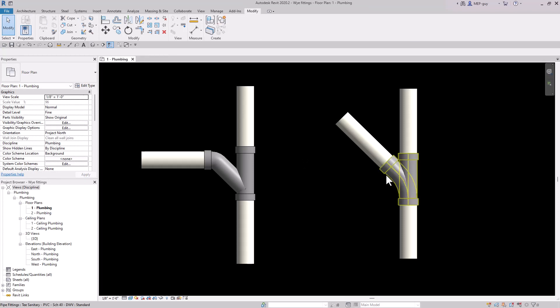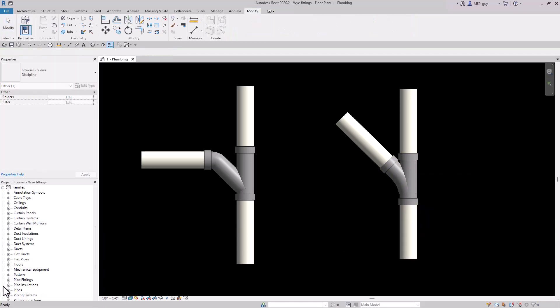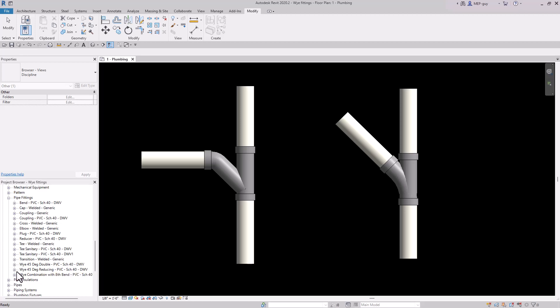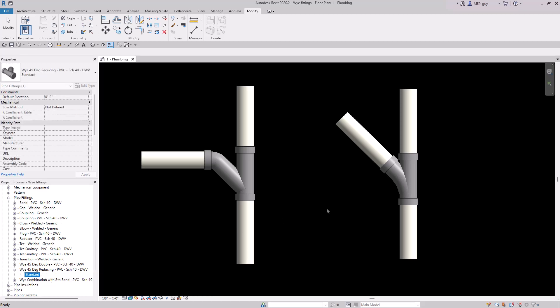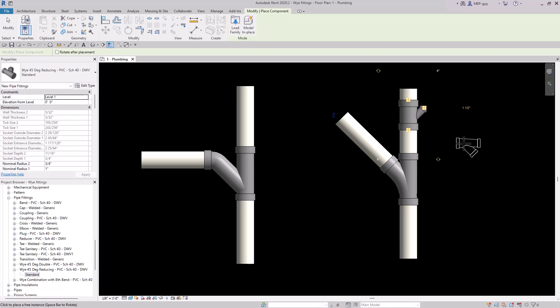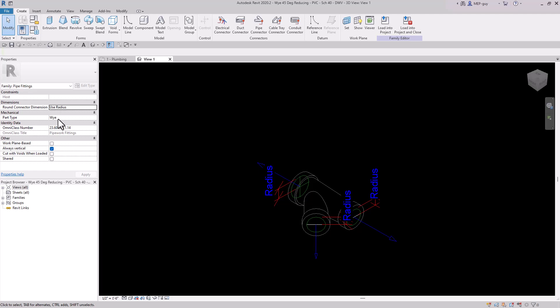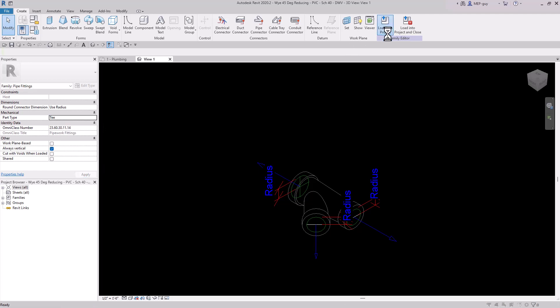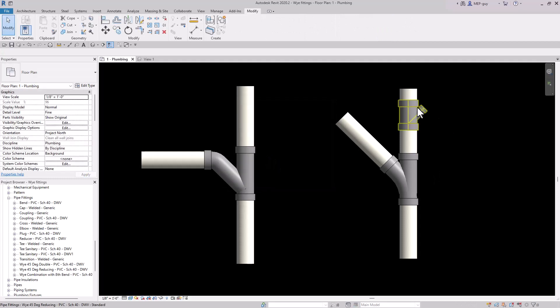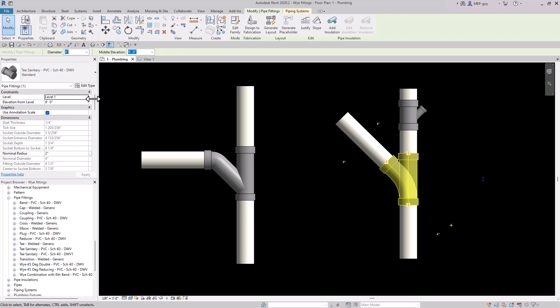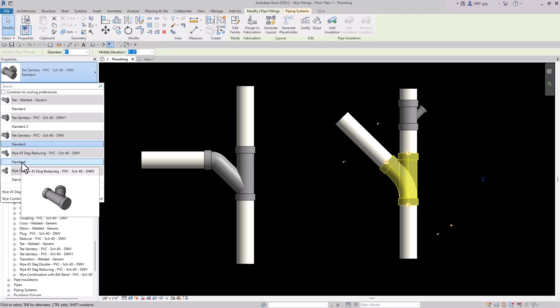What we have to do is change the Y fitting's part type to a tee. Go to Pipe Fittings in the project browser, drag in the Y 45 degree reducing fitting into a piece of pipe, click on it, and go to Edit Family. You can see this fitting is a Y type — but we want to change it to a tee. Now let's load it back into the project, overwrite the existing and its parameter values. Now it's a tee fitting, and if we click the dropdown on our fitting it is now available. We change it to that tee — and everything worked out perfectly.